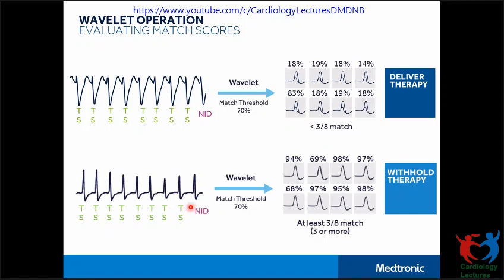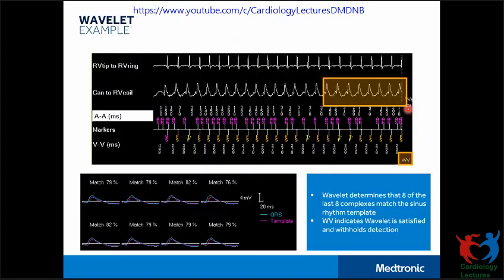On reaching the NID, it will look back at eight beats, and if it finds that at least three or more of the eight beats show a match criteria, it will withhold the therapy and classify the rhythm as SVT. If it finds that fewer than three of the eight beats match, it will go ahead and give therapy. In this example, all eight beats show match scores above 70 percent, so the device withholds detection and marks it as 'WV,' indicating therapy was withheld because of the Wavelet feature.